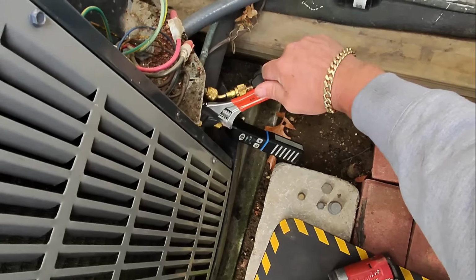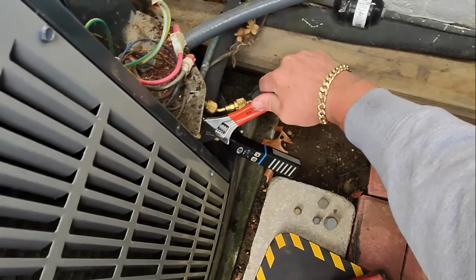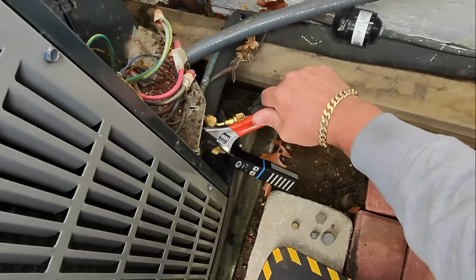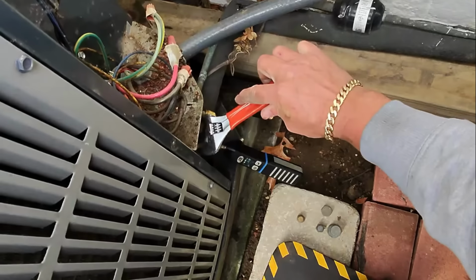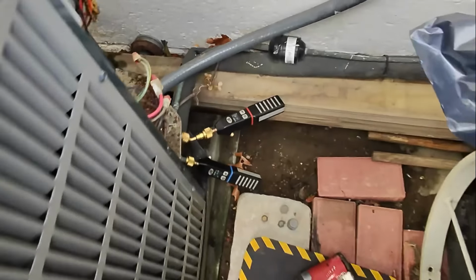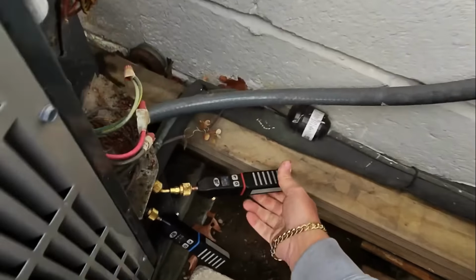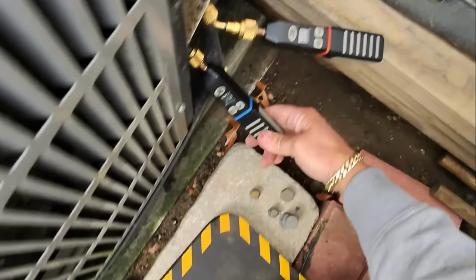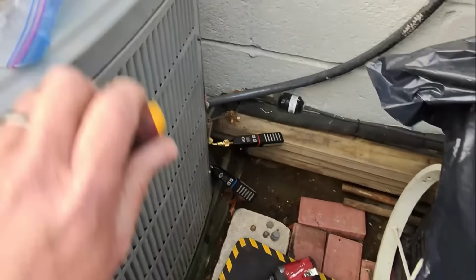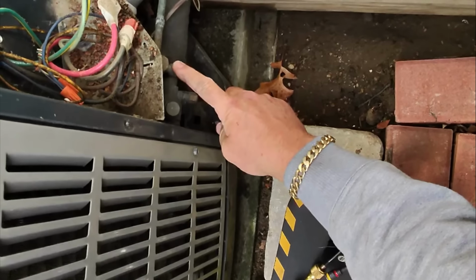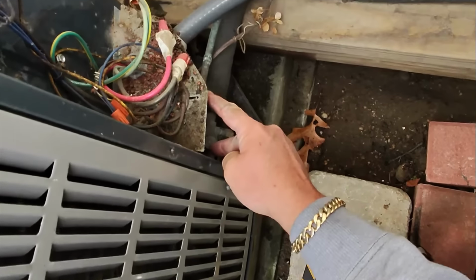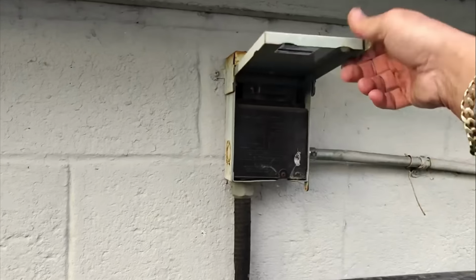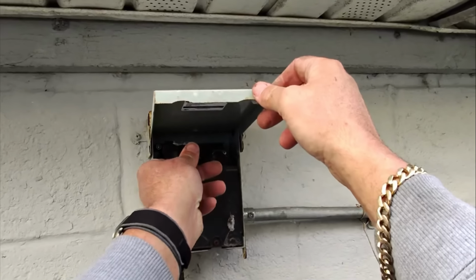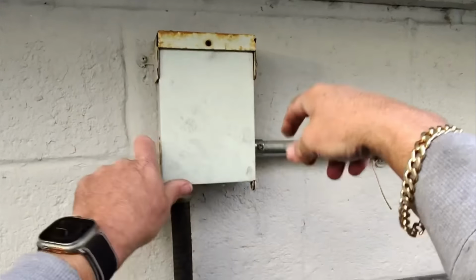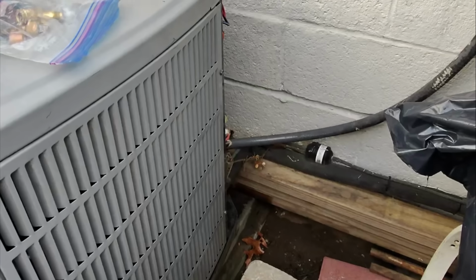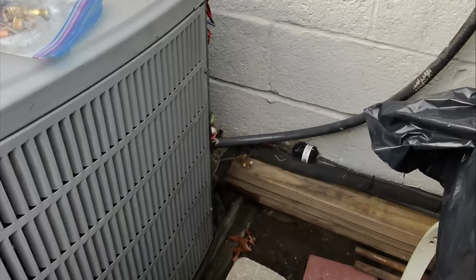Negative pressure. Let's keep going a little bit longer. Negative pressure on both sides. Let's close the valve. Okay, we have pumped down. -5, -5. Beautiful. I have my service port caps back on. The caps covering up the valves. Let's open up the disconnect. Let's pull the disconnect. Let's flip her upside down. We don't want this thing accidentally running. Put the cover back on and let's head on inside.